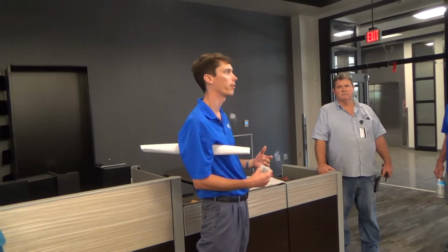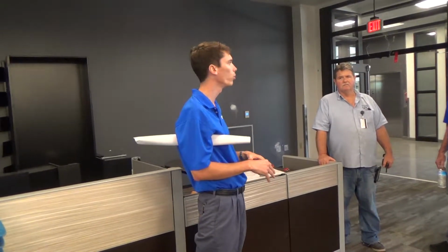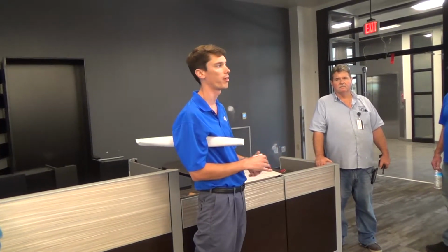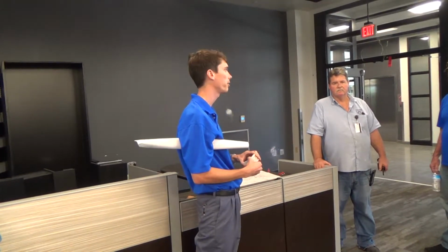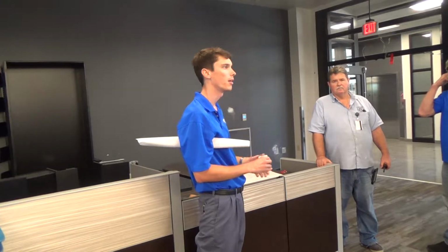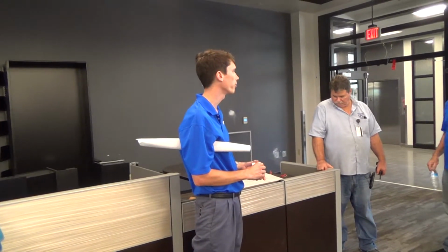the BMS system. So the AC guys are looking at our sensors to see if areas need to be cooled, or when they need to be cooled, or when they can turn it off based on occupancy. And everything in the space right now is controlled on occupancy or override switch. We have the ability to put time functions on, but you're going to recover the most energy savings with occupancy.